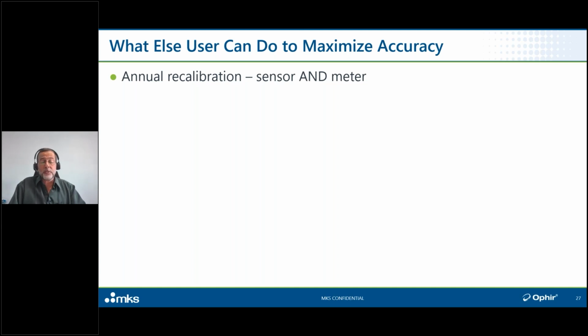The meter is also a precision measurement instrument. It's not just a display. Years ago, we used to call it a display, but we changed and we started calling it a meter because in essence, what it really is, is a very smart picoammeter with a lot of functionality added, but it is a precision measurement instrument. True, its contribution to the final overall uncertainty is only about plus minus 0.25%, plus minus 0.5% when it's more than a year old, which is much less than the contribution to inaccuracy of the sensor, which is typically plus minus 3%, but still, if it's not periodically recalibrated, this can certainly increase and become a potential issue.